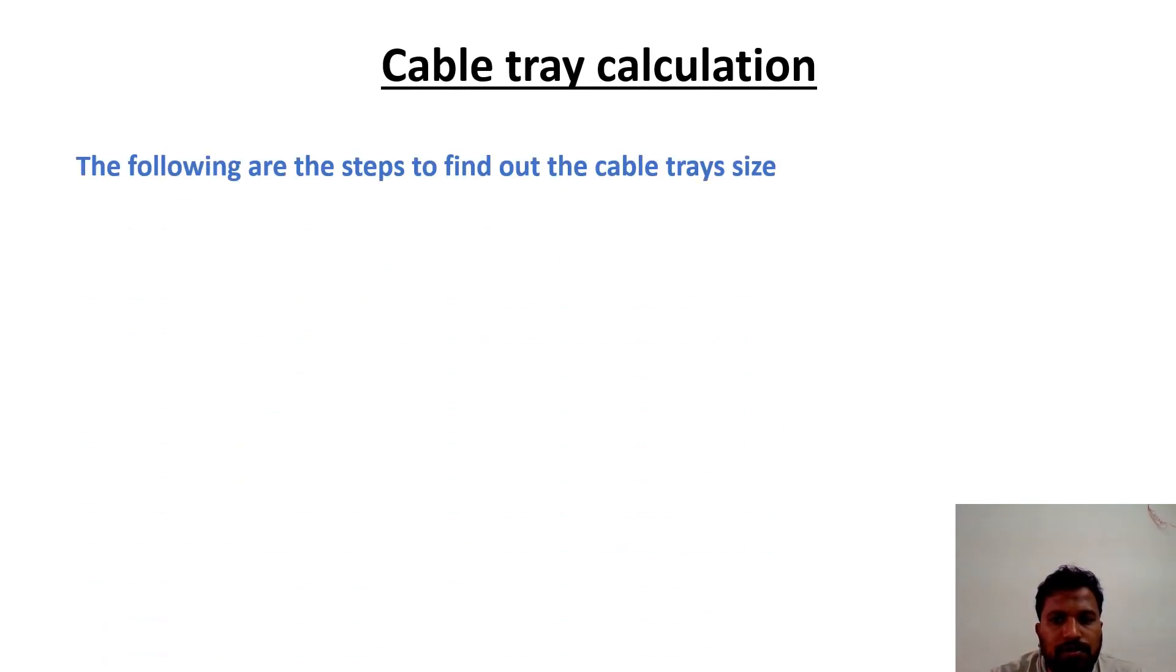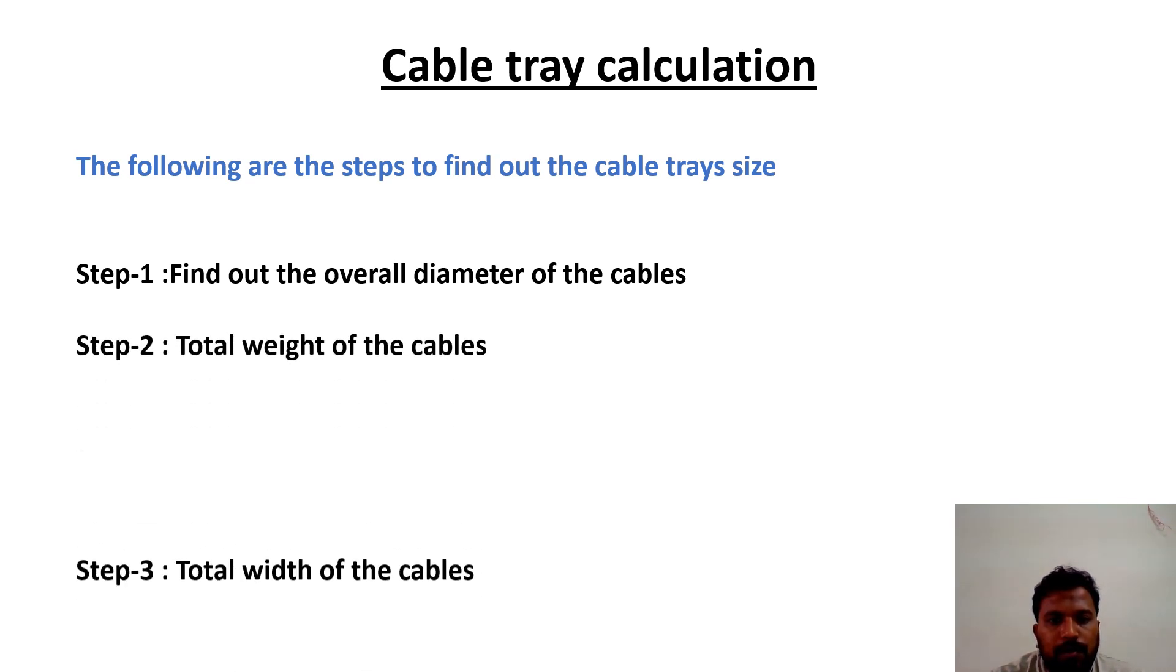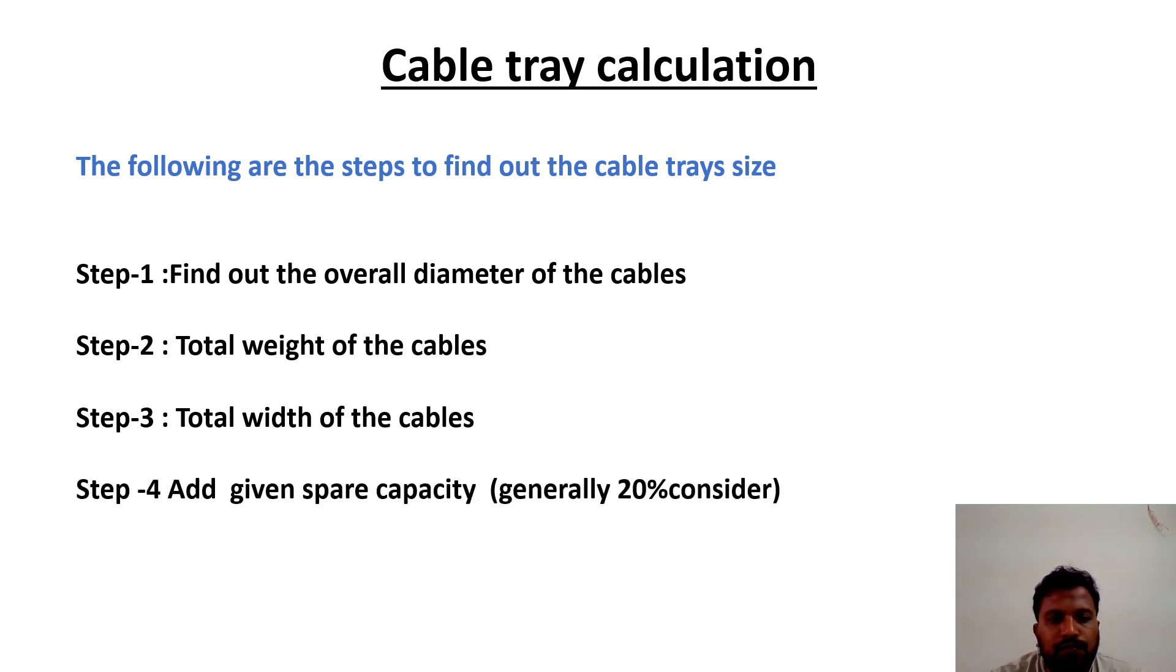Cable tray calculations. To find out the cable tray calculations, we have a 4-step process. Step 1: find out the overall diameter of the cables. Step 2: total weight of the cables. Step 3: total width of the cables. Step 4: add a given spare capacity. Then choose the cable tray size.